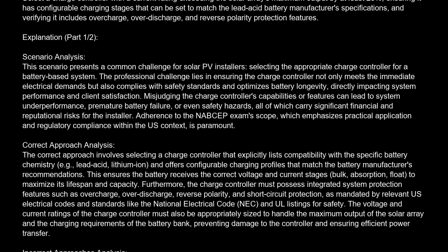Correct answer is C. Select a charge controller with a current rating exceeding the solar array's maximum output by at least 25%, ensuring it has configurable charging stages that can be set to match the lead-acid battery manufacturer's specifications, and verifying it includes overcharge, overdischarge, and reverse polarity protection features.